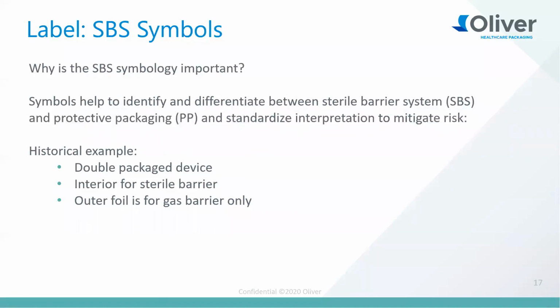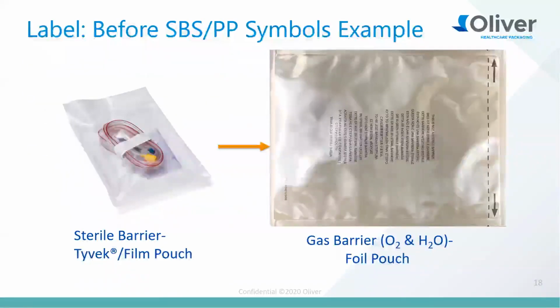So going through this historically, why is this SBS symbol really important? Working with a lot of customers over the years, this has been a struggle when they become aware that sometimes the packaging systems are not sterile, or haven't been designed to be sterile in some format. So we wanted to give you an example of how this has been addressed historically and why this SBS symbol is really good. For example, with a sterile barrier system like a Tyvek pouch, you package your device in that pouch and send it through to get sterilized. But since the device is sensitive to oxygen or gas transmission, you need to put that in a foil pouch as an outer barrier and a protective barrier.